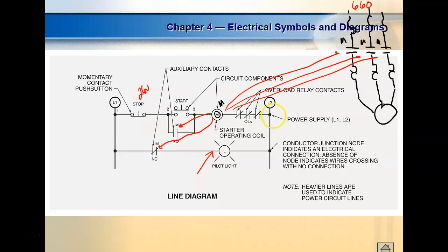Well, technically, we consider L2 to be the common. So that's why when we look at ours, this guy right here is fused. Now, a lot of industrial controls will fuse both sides. Normally, when you get up to a certain voltage, you have to fuse both your neutral, your common side, and your power side. So yeah, this is L2, considered the common.